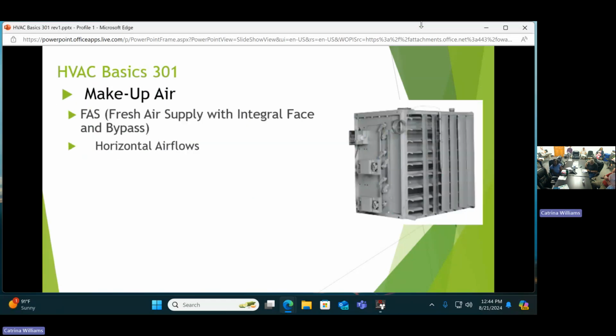Here's your fresh air supply unit. This particular picture shows a horizontal model. The coils we just talked about were 5/8 inch tubes. We're now using 3/8 inch tubes for these hot water and steam units. They're smaller boxes, smaller coils, and the 3/8 inch gives us the heat capacity that we need.